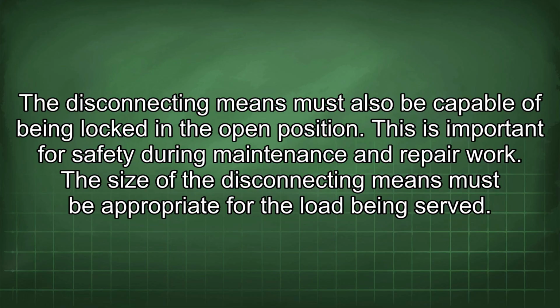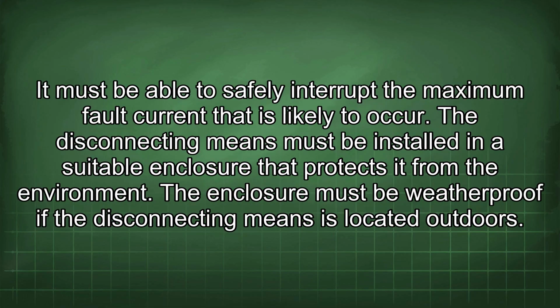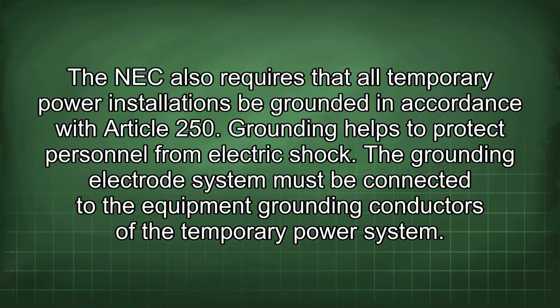The size of the disconnecting means must be appropriate for the load being served. It must be able to safely interrupt the maximum fault current that is likely to occur. The disconnecting means must be installed in a suitable enclosure that protects it from the environment. The enclosure must be weatherproof if the disconnecting means is located outdoors. The NEC also requires that all temporary power installations be grounded in accordance with Article 250.